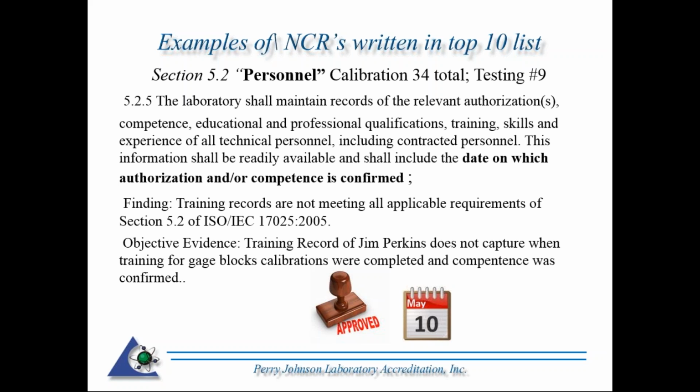So in other words, I always specify it this way, and I'm a calibration program manager, so I do a lot of calibration labs. So if I'm looking at a technician demonstrate a gauge block calibration, and this lab might do a lot of other calibrations, like mechanical, electrical, various dimensional type of calibration, but somewhere along the line is to say this technician was employed for about a year, he's gone through the training, he is now determined competent to perform calibration on behalf of this calibration lab. I'm looking for that date of competence to be captured.